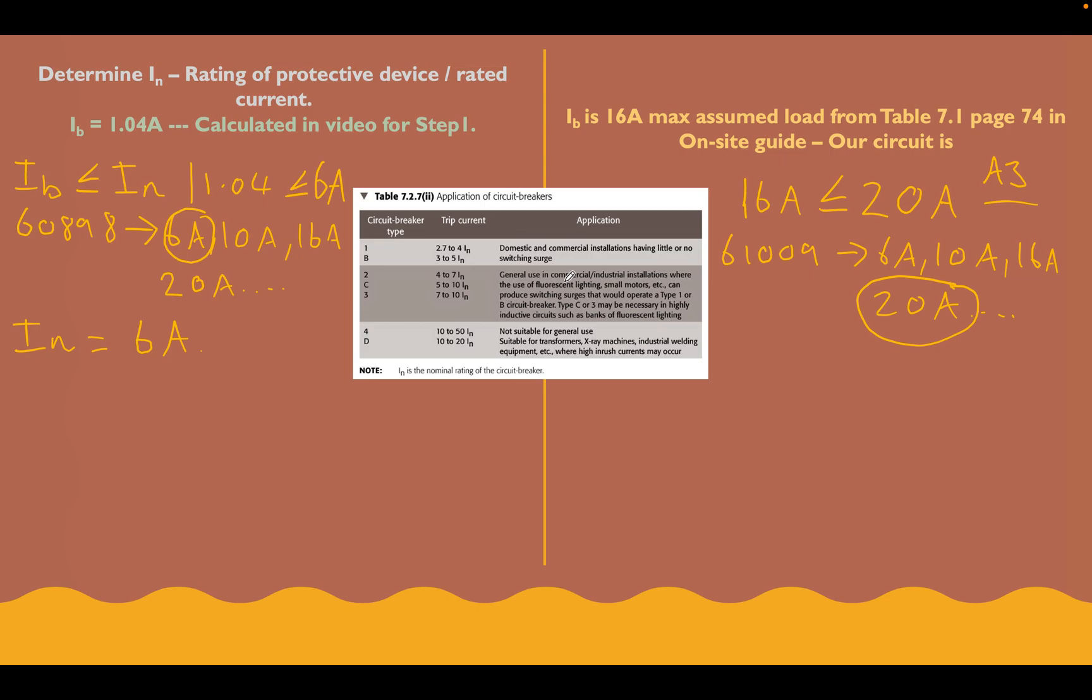What they're saying there is that these fluorescent lights or motors, when you switch them on and they first start up, there's a large current flow initially for when they first turn on. So that's why we'd select a circuit breaker like a type C, which allows for those large switching surges. A type B - in this bit where it said it'd operate a type 1 or type B, when it says operate, it means it'd trip it out essentially. So it's saying if we had a type B circuit breaker and we were supplying fluorescent lighting, there's a high chance that when we switch it on, that switching surge is going to trip this out.